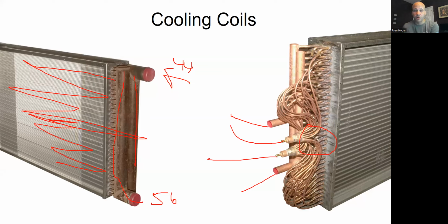And just like we said before, be careful because the hot water coil looks exactly like this one, right? You need to know if it's chilled water or hot water. Ways to figure that out. One, if it's chilled water, it'll have a condensate pan under it to collect moisture. A hot water coil won't need that, although they could have put one there, but it's not likely they would have paid for that. They don't need it.